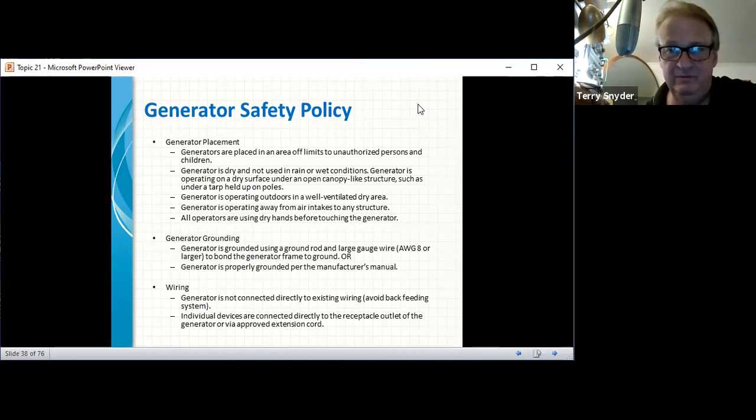If you don't shut off the breakers to the outside world, that 240 line goes through that pole transformer backwards, and the guy working on the power line where he thinks it's shut down is now going to be in danger of a 7,000 volt shock. That's because a transformer isn't just a one-way device. They go both ways.